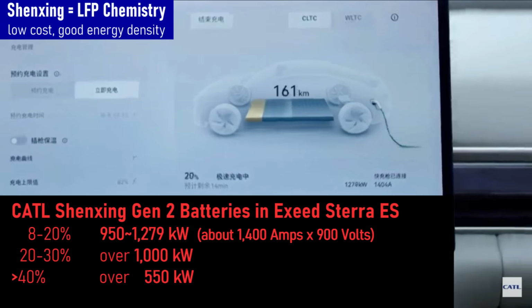1,279 kilowatts is the highest number I saw, so that's a little over 900 volts for the system. When it goes over 20% state of charge, it does drop off, but still over 1,000 kilowatts. It dips below 1 megawatt after 30% SOC, and over 650 kilowatts at 50% state of charge.